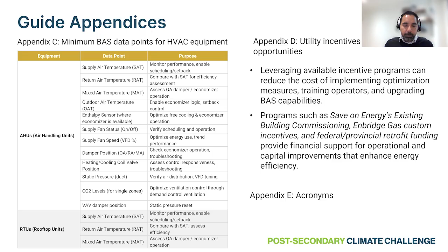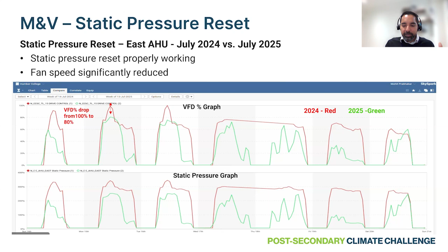So here are some results, as we talked about, with the optimization piece. The first example here is a static pressure reset. As you can see in the top graph, the red line is the VFD speed in 2024, and then when the static pressure was optimized, the VFD speed, which is the green, in 2025 dropped. The peak VFD speed was 100%, and it dropped to 80% once the static pressure reset was changed. The bottom graph shows your static pressure set points: the red is the 2024 set point for a week, and the green is the 2025 set point.